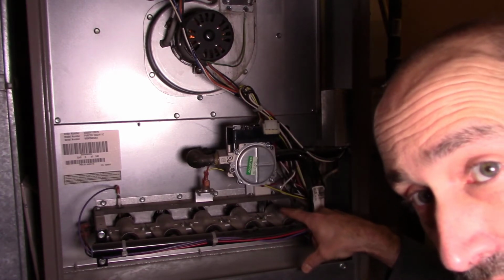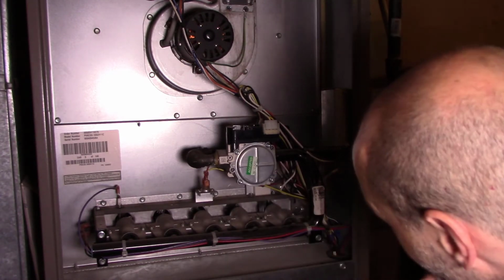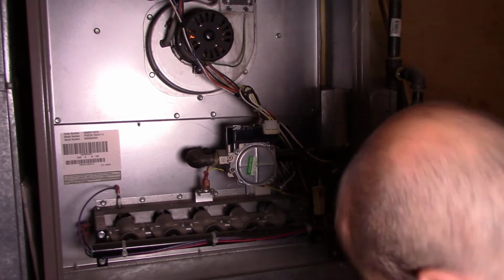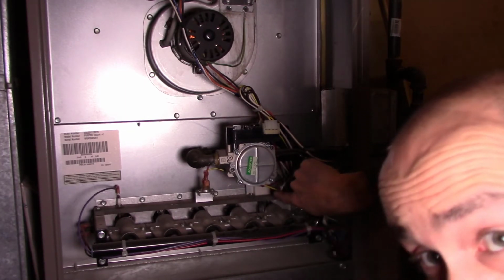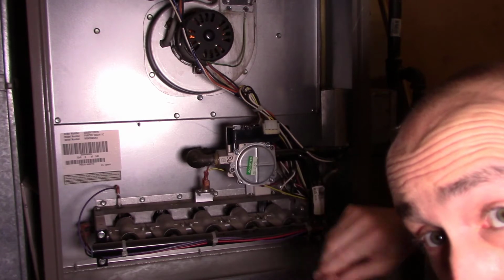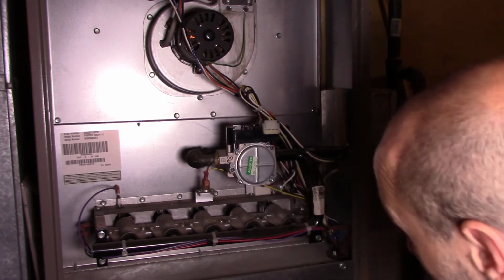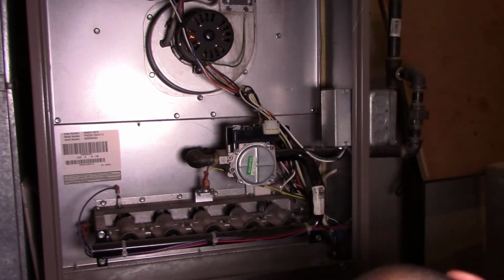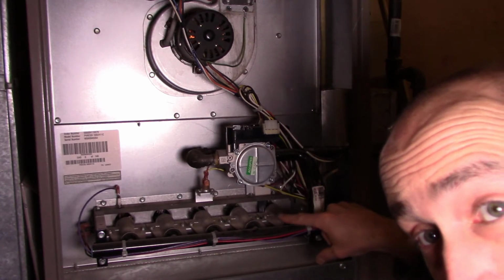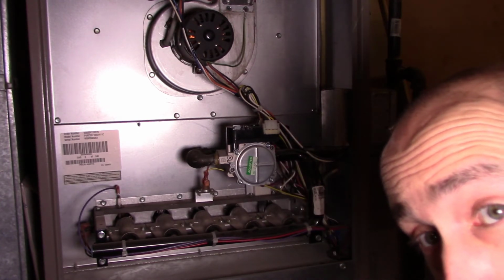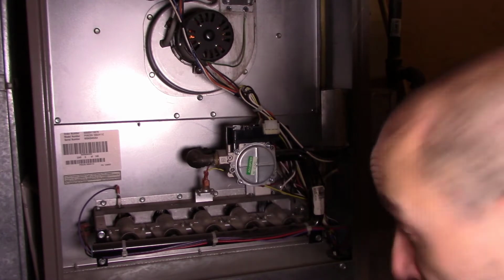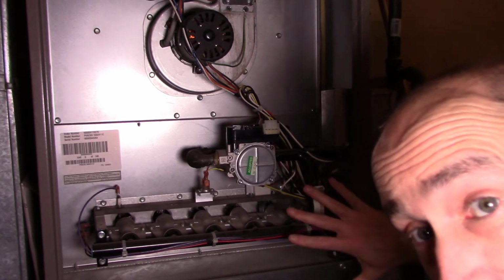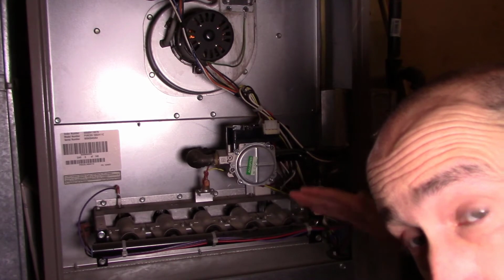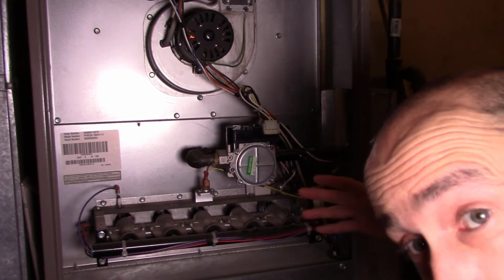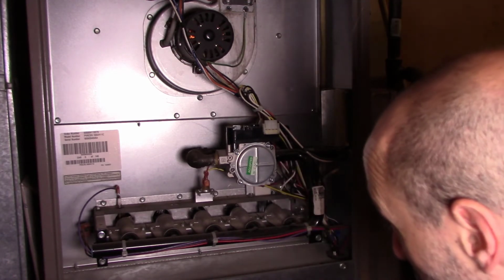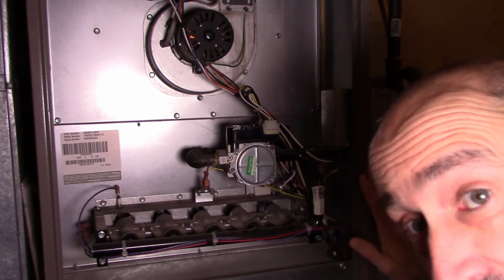Now on those tungsten style ones that glow, typically it's just held in by a screw and a couple of wires, so you can unscrew it, unplug it, and carefully pull it out of there. I'm not going to do that now, but typically what you'll see is a crack in that element, and then you'll know that that's bad and that's the problem. So if your igniter doesn't start glowing or clicking, then you know the igniter's the problem.